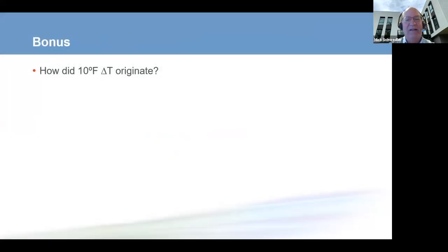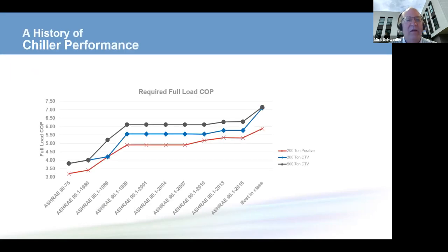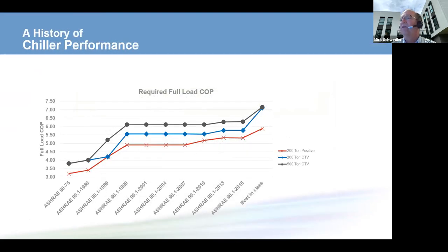So those are the pick six, but there's a bonus. And this bonus is we've done some investigation and I've had a chance to look all over many countries. And I always ask in a chilled water seminar, does anybody know where the 10 degree delta T came from? And what we found, we saw in the ASHRAE green guide and we saw ASHRAE 90.1 is that they're telling us to increase the delta T's and decrease the flow rates. The real driver is chiller performance.